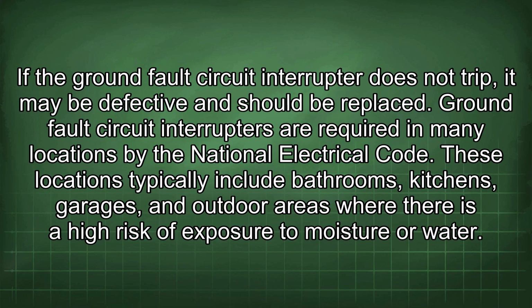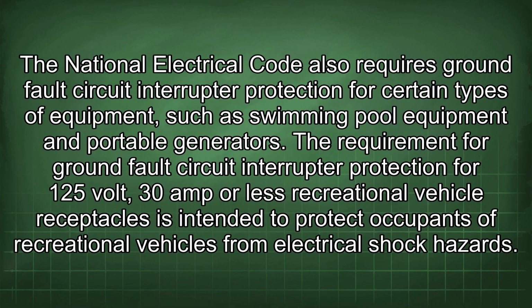Ground fault circuit interrupters are required in many locations by the National Electrical Code. These locations typically include bathrooms, kitchens, garages, and outdoor areas where there is a high risk of exposure to moisture or water. The National Electrical Code also requires ground fault circuit interrupter protection for certain types of equipment, such as swimming pool equipment and portable generators.